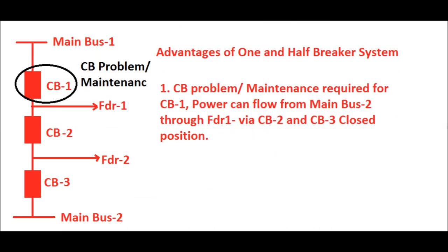In the one and half breaker system, two feeders are controlled via three circuit breakers. Isolator and CT positions have been omitted from the diagram for ease of understanding. This type of system is used in 400 kV GIS systems and also in 765 kV AIS substations.